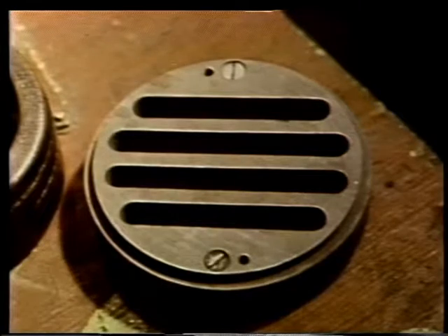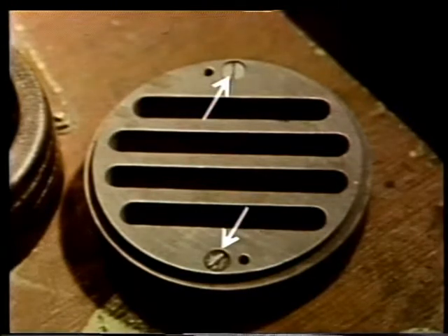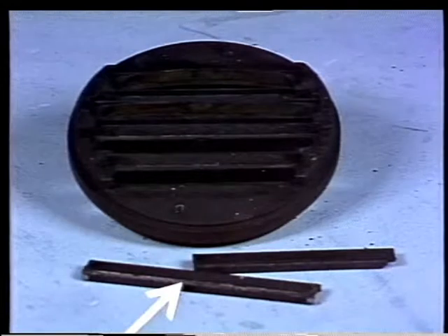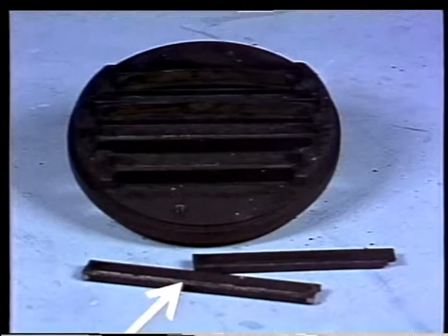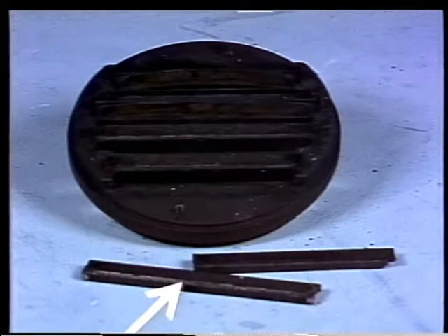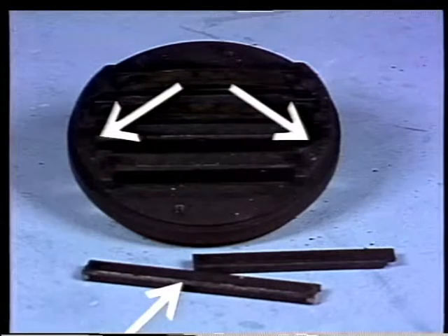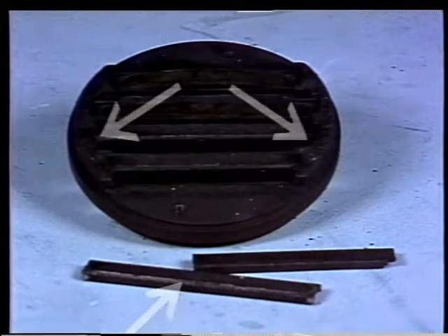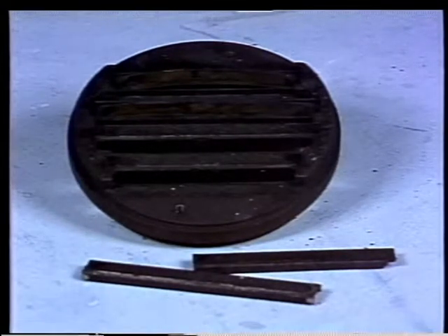To take the valve apart, you remove these two screws on the valve seat. But be careful that the parts inside the valve don't fall out. If you're not going to replace the channels, mark them so you can be sure to replace them in the correct channel guides. Now, this is important because each channel rubs against its guide in a particular way, forming a wear pattern. The friction between the parts causes this. Changing channel positions could interfere with the efficient operation of the valve.